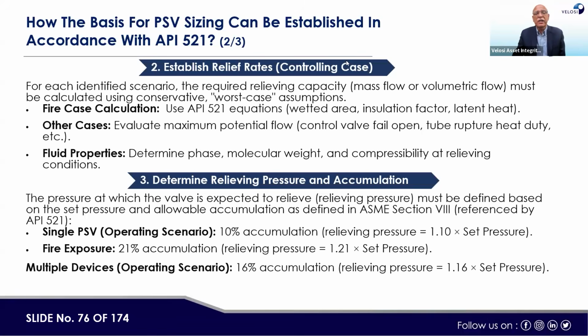Here, first establish the relief rate and the controlling case, whether outlet blocked, fire scenario, heat exchanger failure, or any other failure which may overpressurize the system. Then determine the relieving pressure and accumulation. For single PSV operation, 10% accumulation, which is 1.1 times the set pressure. For fire exposure, 21% accumulation is allowed, 1.21 times the set pressure. For multiple devices, 16% accumulation, which means 1.16 times the set pressure.